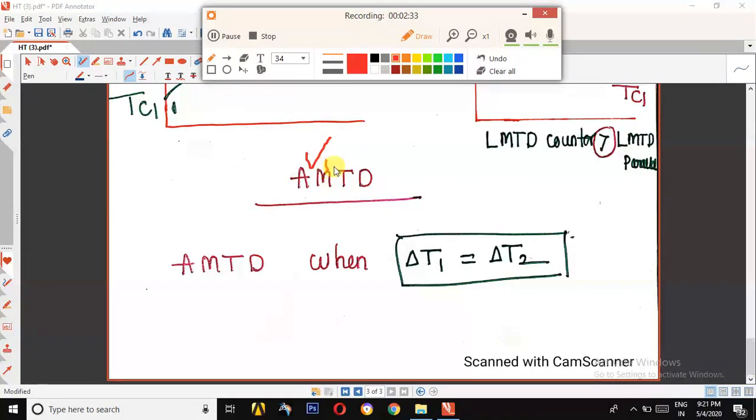Arithmetic Mean Temperature Difference. If we use AMTD instead of LMTD, we will get over estimated values of temperature difference. Therefore, design of heat exchanger will fail. We can use AMTD only when delta T1 is equal to delta T2.